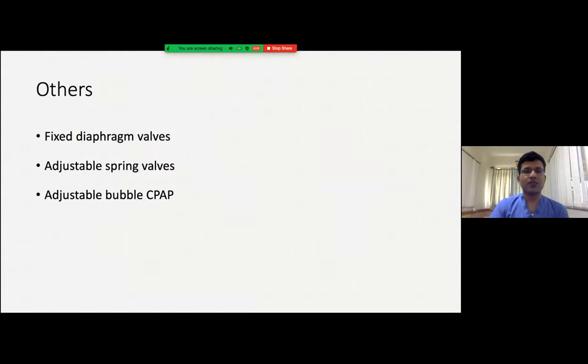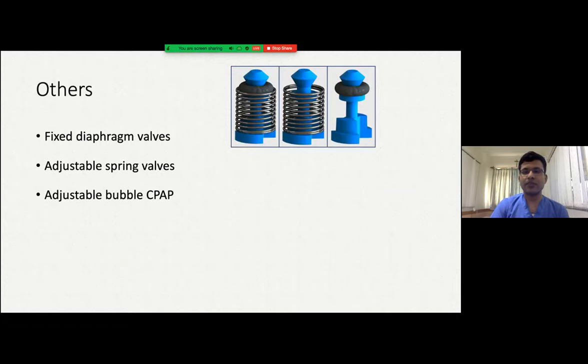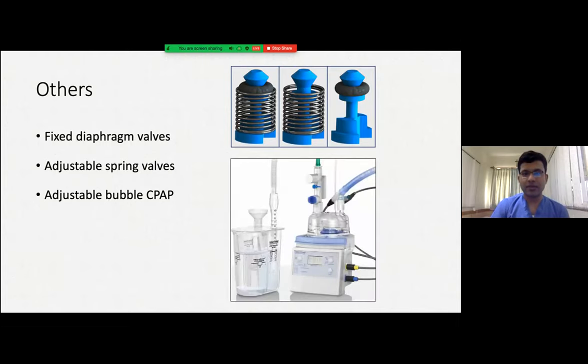There are other types of valves which can also provide PEEP: fixed diaphragm valves, which are the older version and seldom used nowadays, and adjustable spring valves. These can be seen in the PEEP valves of Ambu bags. We also have bubble CPAP, where pressure is regulated by the depth of insertion of the expiratory tubing into the water channel — the depth of insertion is equivalent to the PEEP.